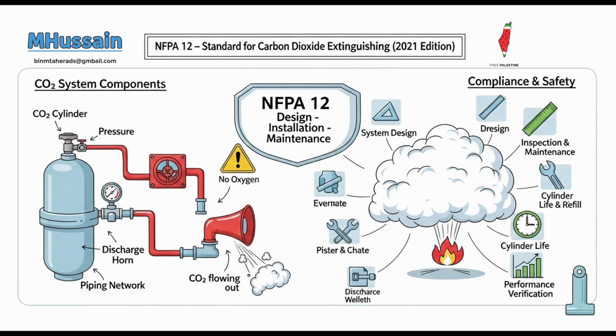The implication of adding new piping equipment, like these lockout valves and time delays, is significant. It increases the equivalent pipe length within the system. More pipe changes the flow. Exactly. This then requires the system's original flow calculations to be meticulously re-verified to ensure that the agent quantity and discharge rates are still sufficient to meet the design concentrations and discharge times despite the added resistance. So you can't just add safety stuff without rechecking everything. Absolutely not. This emphasizes how deeply integrated safety features are with the core system performance. You can't just bolt on a safety device without potentially affecting how the entire system functions.